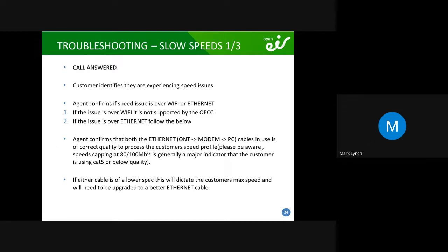So what that results in is that it's like one single lane of traffic going into four lanes of traffic. It's still only going to be one lane of traffic, even though it's opening up at that speed. Same way, if they have the cables the other way around, it's four lanes of traffic going into one lane of traffic, if you just want to think of it that way. But both cables need to be up to spec. And it's actually the biggest cause of failed slow speed faults that we see, is caused by Ethernet cabling. If either cable is of a lower spec, this will dictate the customer's max speed and will need to be upgraded to a better Ethernet cable.